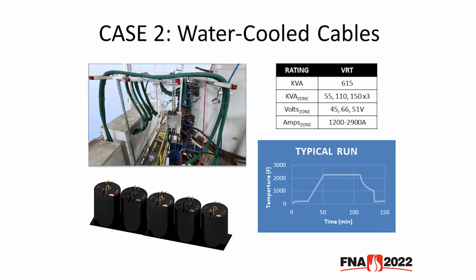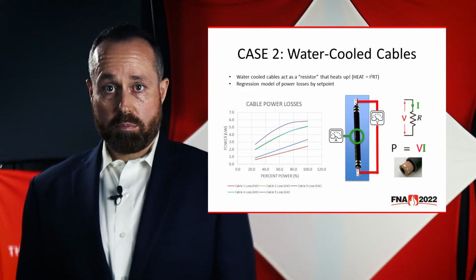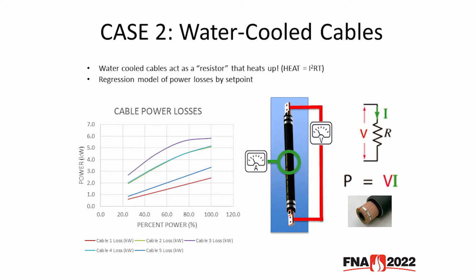The water-cooled cables in this case consisted of 4 14-foot cables, 4 18-foot cables, and 2 20-foot cables. In the picture here, you can see the cables draped over the catwalk between the VRT power supply and the furnace chamber. The power loss in the cables was then measured across multiple furnace set points. The power loss was calculated by measuring the amperage and voltage drop across the cable. Power loss is then calculated by taking the product of that voltage drop and the amperage.